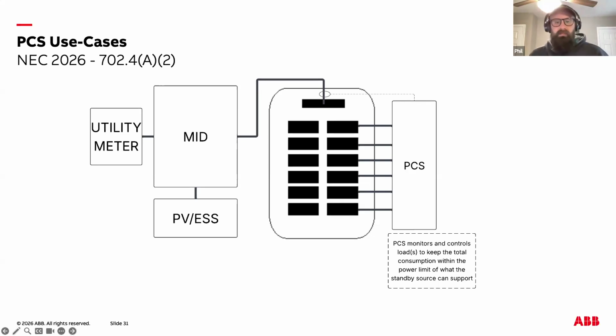tighten. An automatic optional standby system must either be sized to carry the entire automatically connected load, or it must use an energy management system to automatically adjust the connected load so that it never exceeds the output capability of the standby source. This is where power control systems become essential.